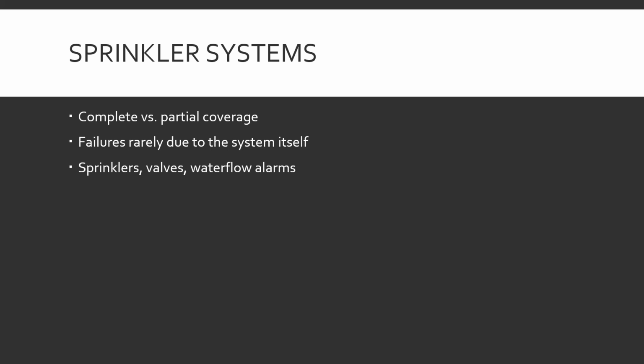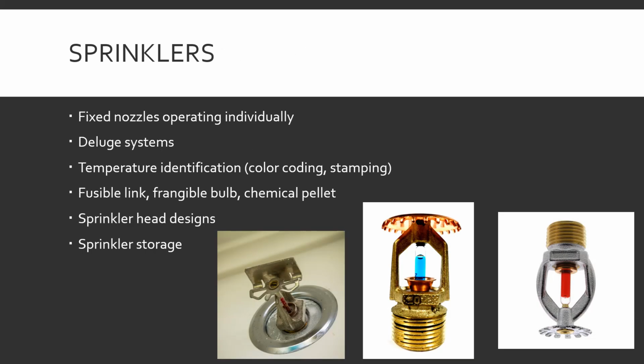How they fail, why they fail: sediment in the water lines clogged them. Someone on a forklift hit a sprinkler head and set off the system. We're going to get to valves. So I'll hold on to one, but usually there's some external force causing the system to fail. They just don't fail like your car being dead when you get up in the morning kind of thing. Sprinklers, valves, and water flow alarms. We'll get there. Those are kind of the hot points. Those are kind of what we're going to be talking about next. Sprinklers.